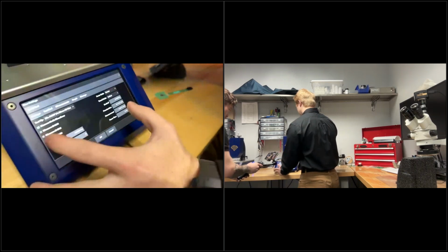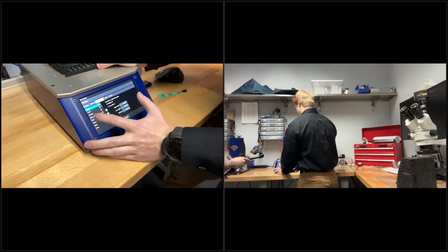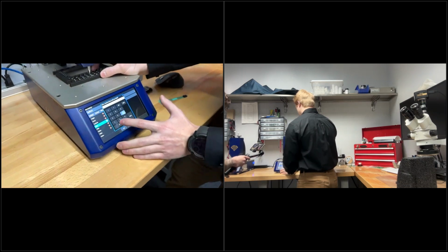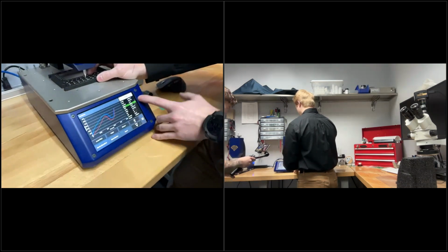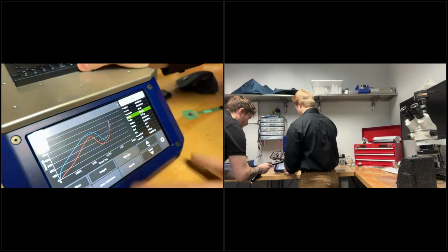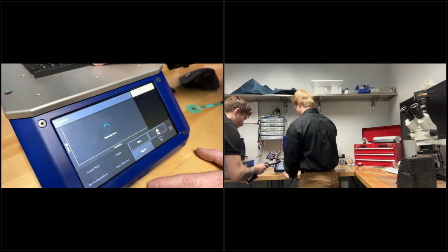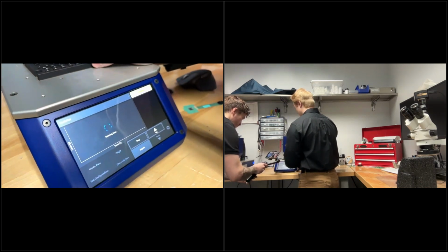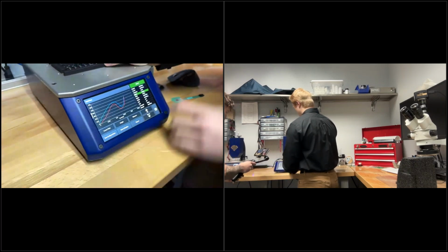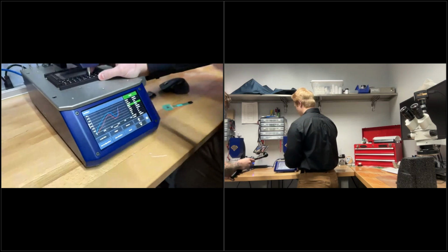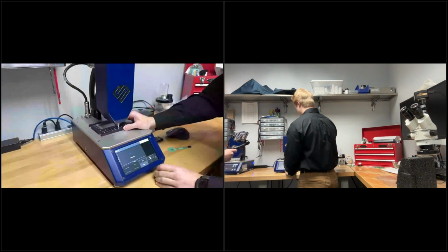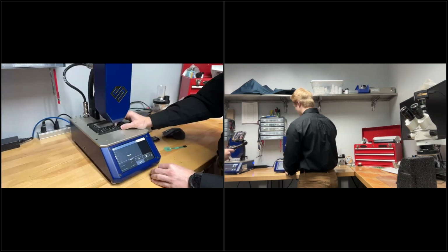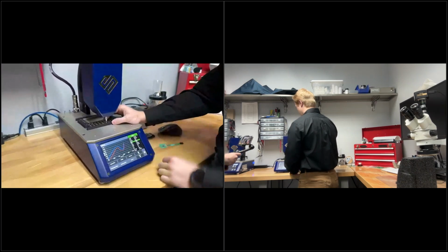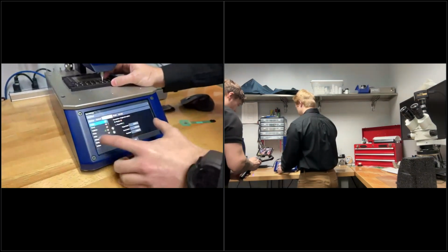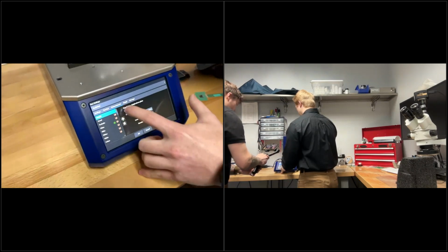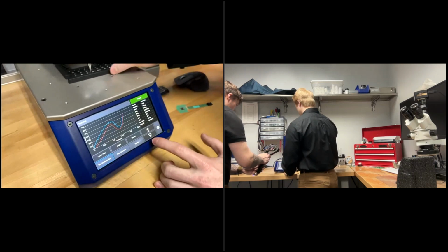So if we go back and adjust that upper threshold for Fmax to, say, 600 grams, it'll come back and it'll paint that as green. And then we can continue to test the different positions and see if these positions fall within that threshold, making it really quick and easy just to distinguish between a good passing part and a rejection failing part. Continue on that, give it a couple examples. So exactly, you can see that that works really well. We'll turn that pass fail off here, since we will be moving on to a different product.